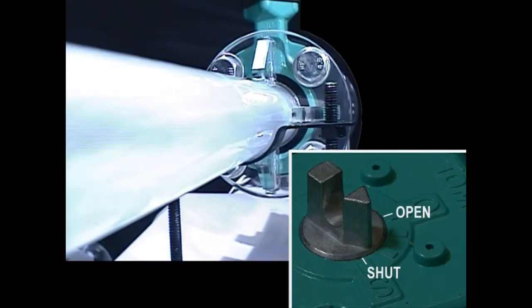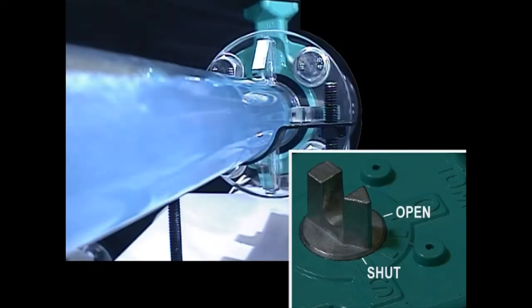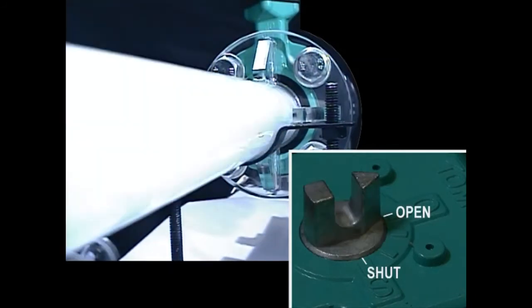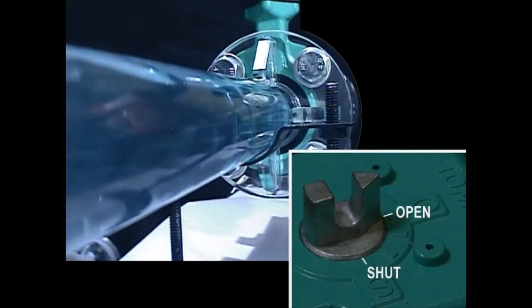In short, open valves gradually by inching, stop when slightly open and observe the state of things for a while. For valve closing, also do it gradually by inching. We can go so far as to say that most of the troubles associated with ballast operations can be avoided unless you open and close valves abruptly.